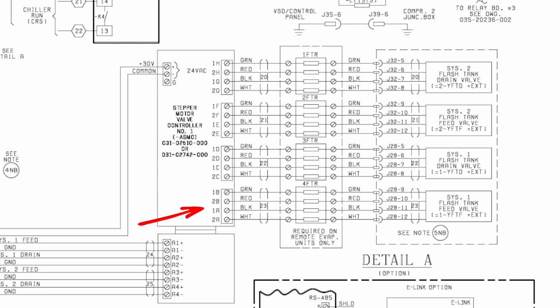Another thing we need to be aware of is the wiring. The majority of the valves that I see implemented in chillers today are typically a 4-wire valve. This particular chiller has 4 different EXVs that it controls, all running through a stepper control valve. This is a separate controller from the main controller in this chiller. In some chillers, the valve will come straight off the main base control board, or you may have a subboard that communicates back to the main board that controls these things. So you could have it either way. Just be aware of that.